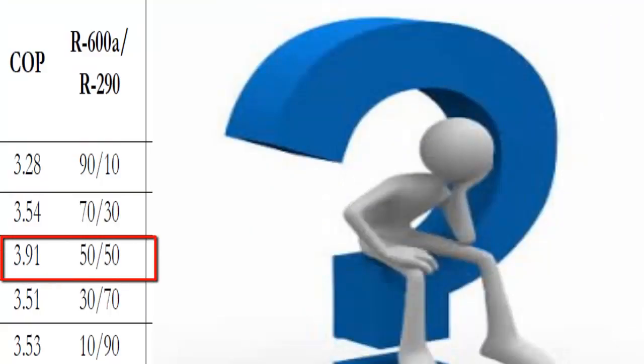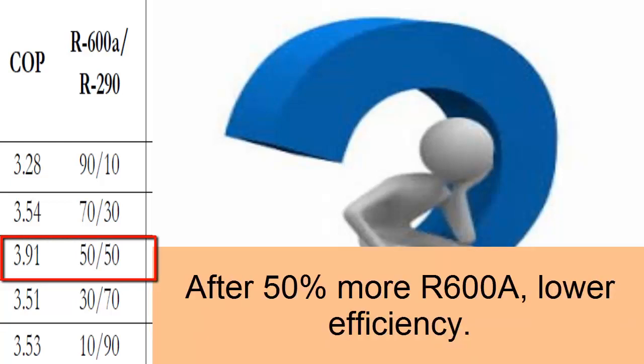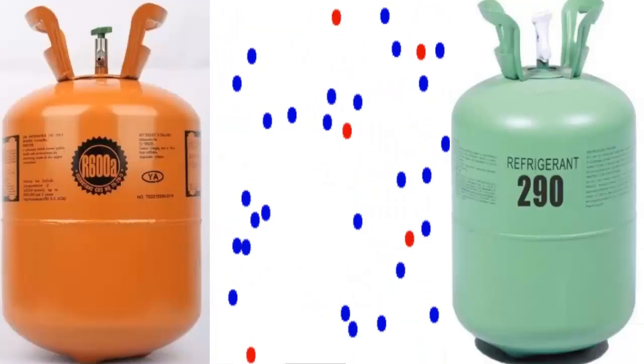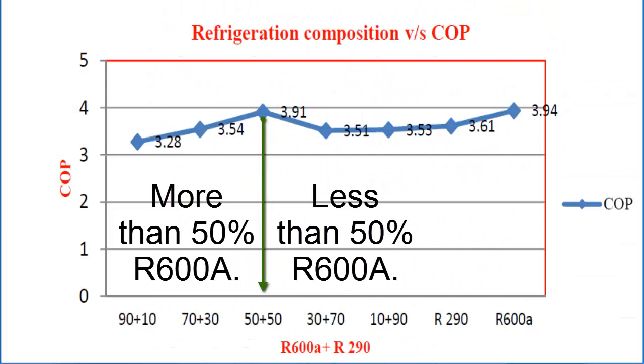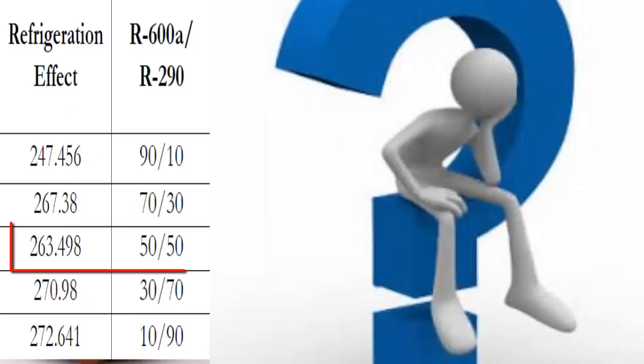After a proportion of more than 50% of R600A, as the amount of R600A refrigerant in the mixture increases, the coefficient of performance of the system — COP — decreases, meaning the system becomes less efficient. On the screen we have different performance values for some mixtures between R600A and R290.